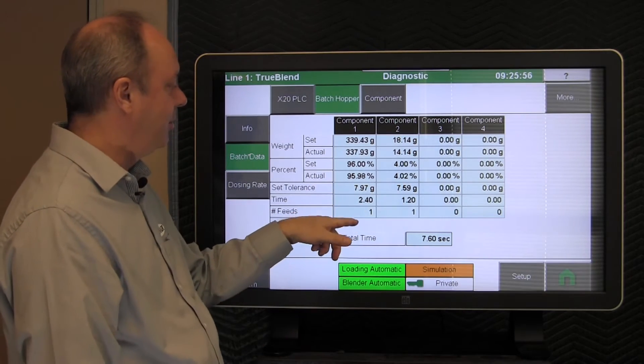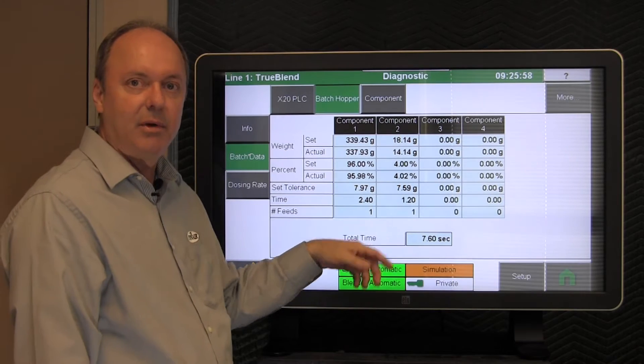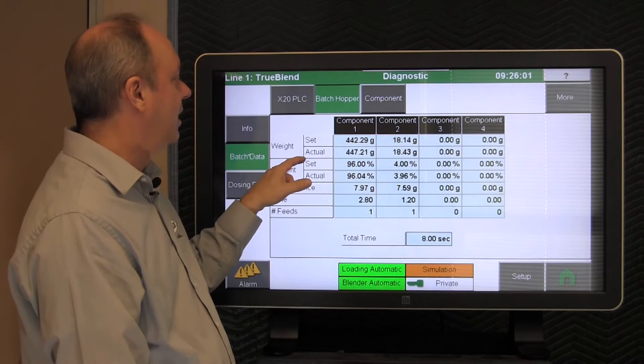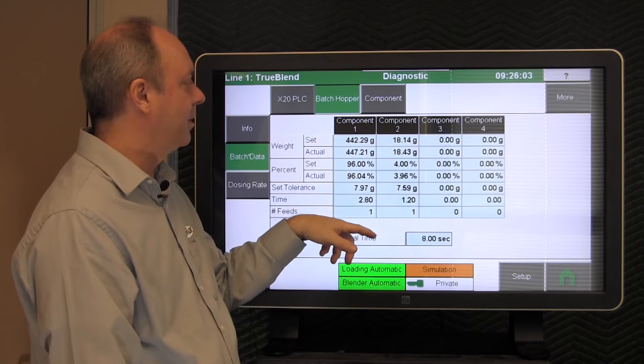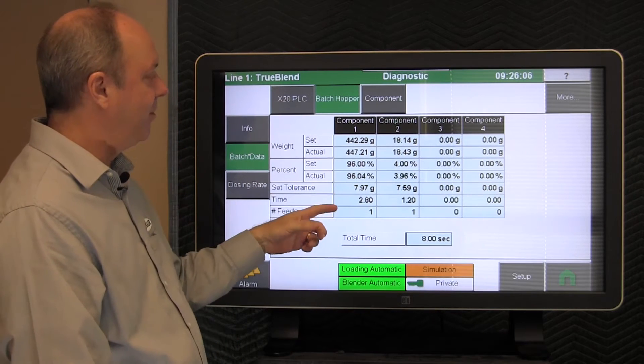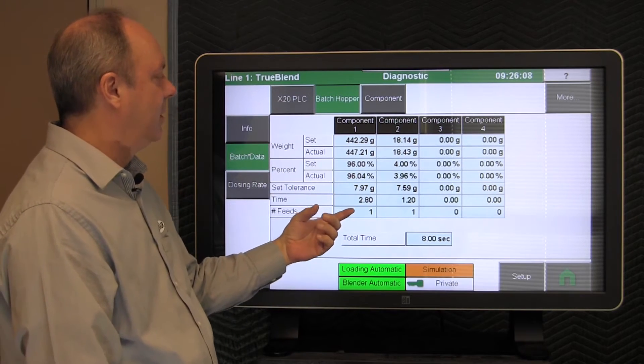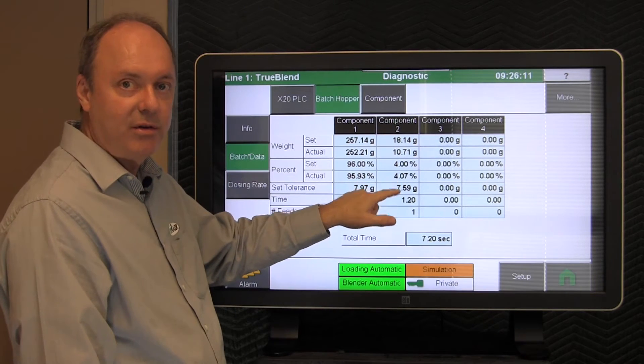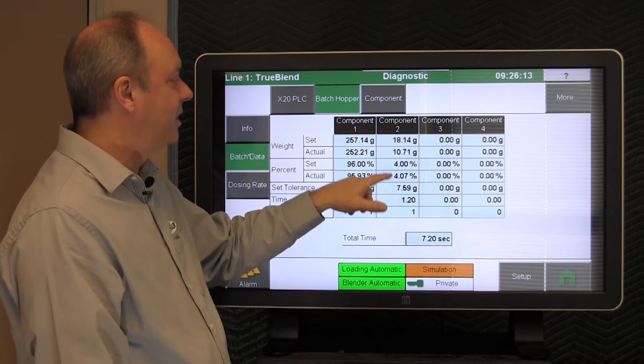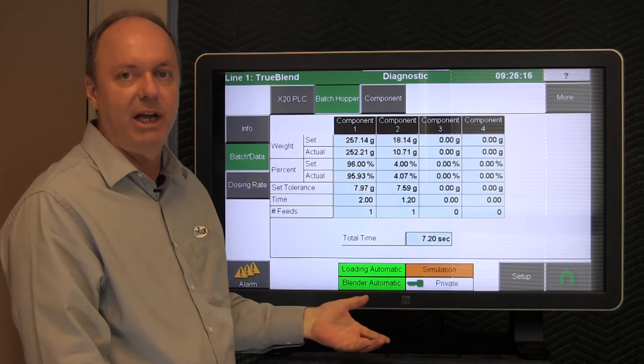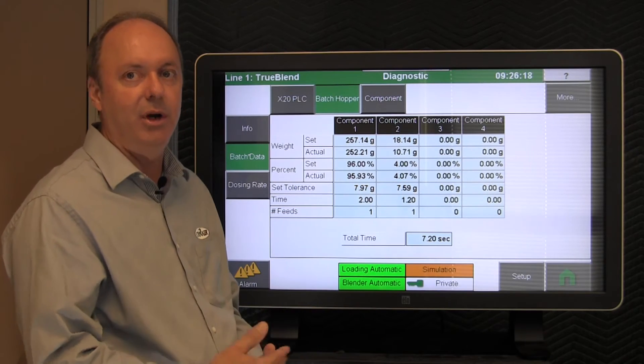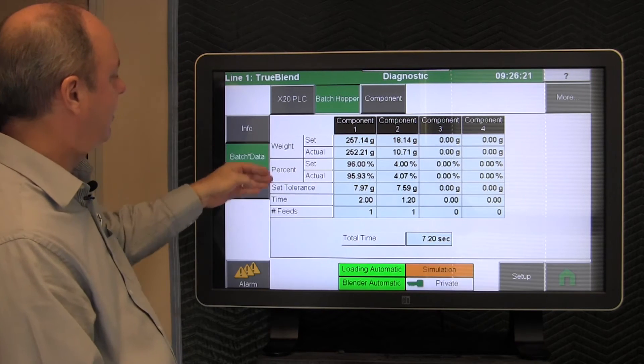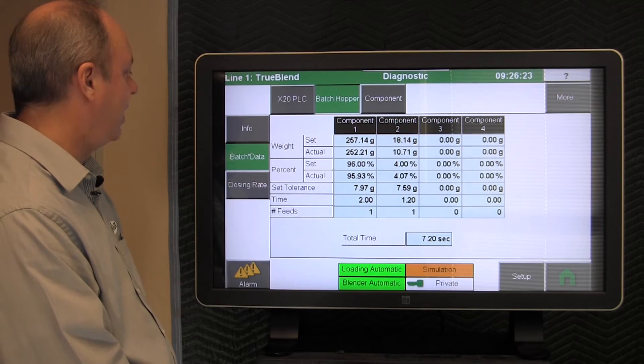In normal operation, you may see more than one dose because the way the system works is it tries to approach this set amount. And if the computer sees that you have yet to feed a value that is greater than its minimum amount that it can dose, then it will dose again. If you get to within the minimum amount that it will dose, it won't dose again. Otherwise, if it did, you would overshoot.